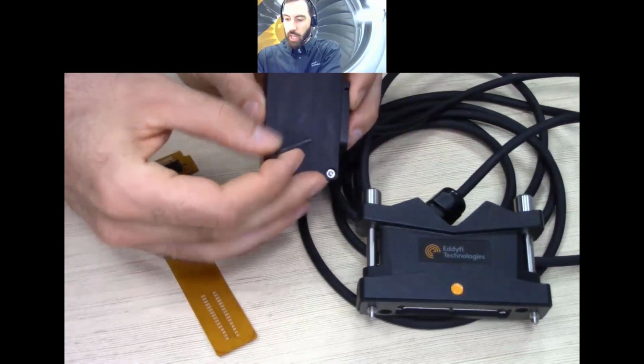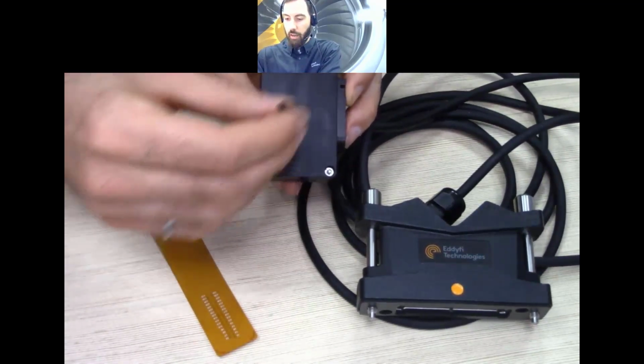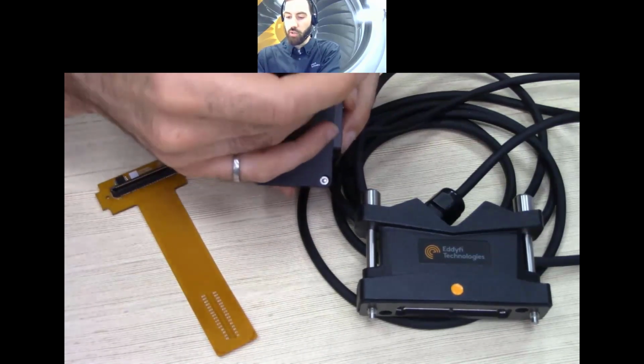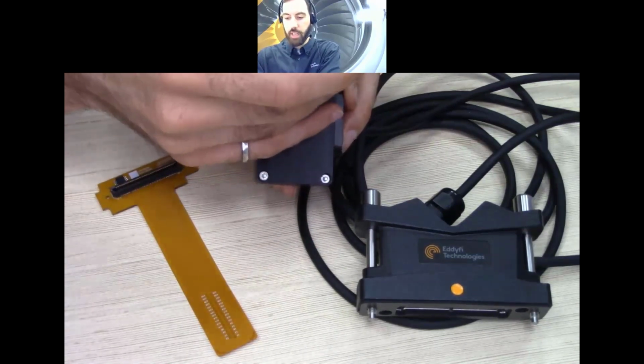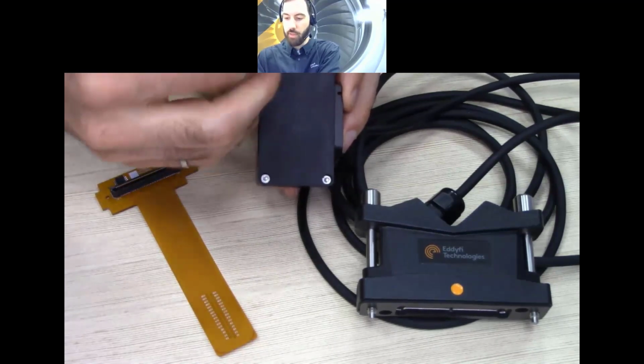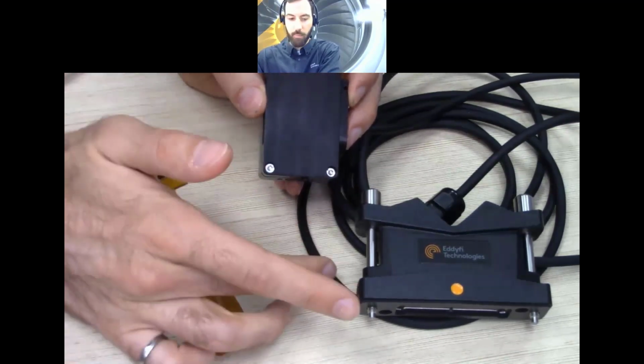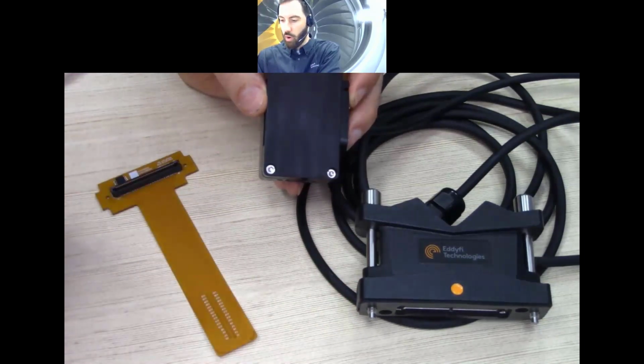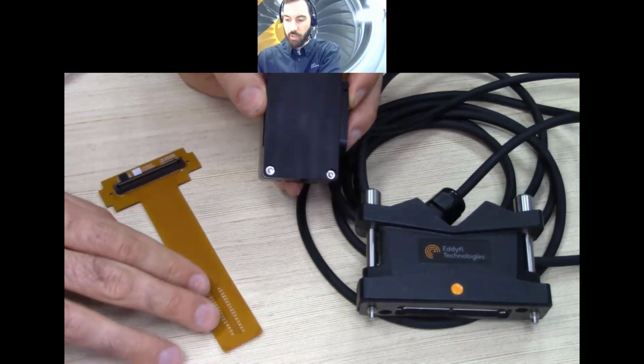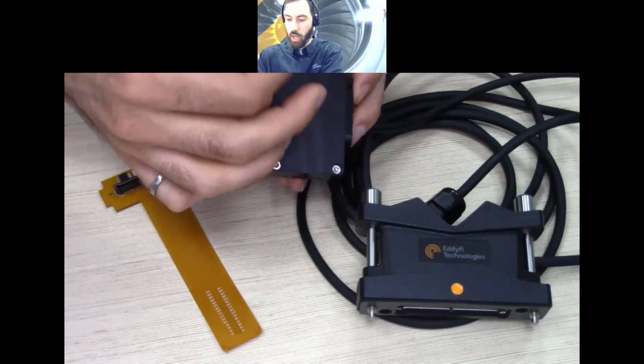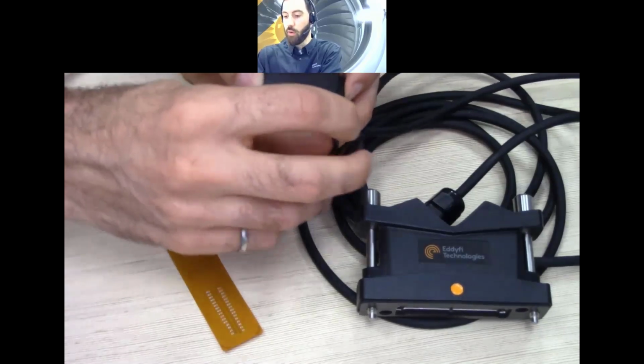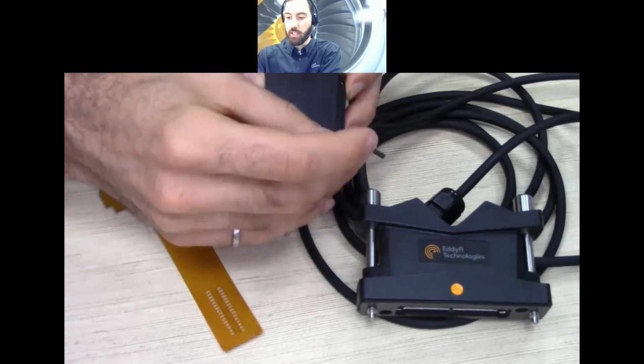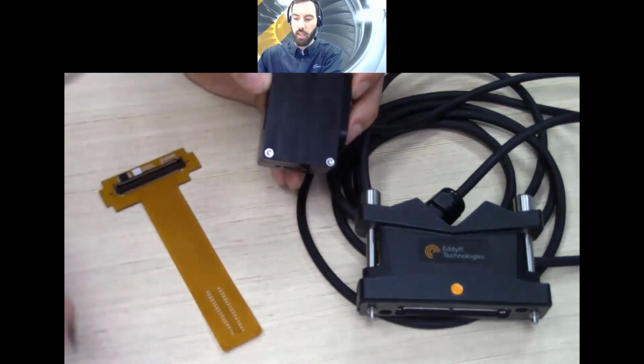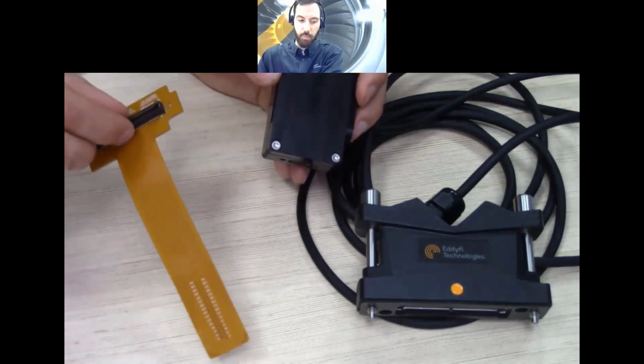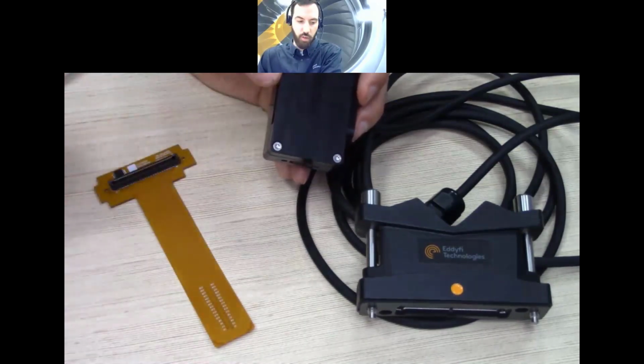So this is not something that you will have to do often, obviously, but the point of making the products modular like that is that if an accident happens, if something gets damaged during an inspection, it can be either the cable getting cut by accident or one of the coil sensors being damaged from a rough surface or a cutting surface. If you have to replace a component, at least you won't have to replace the entire thing. You can just detach the flexible part and replace whichever of the two components is damaged.